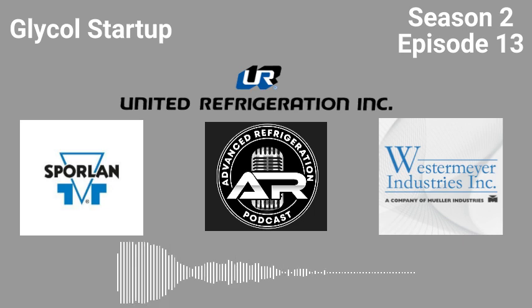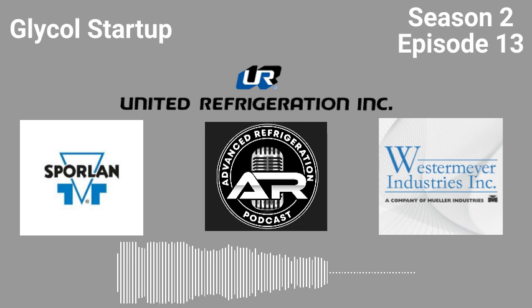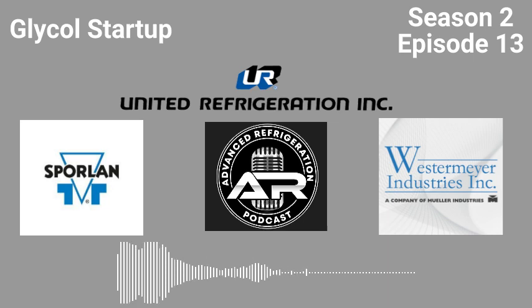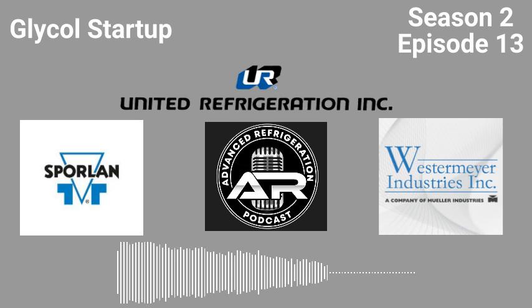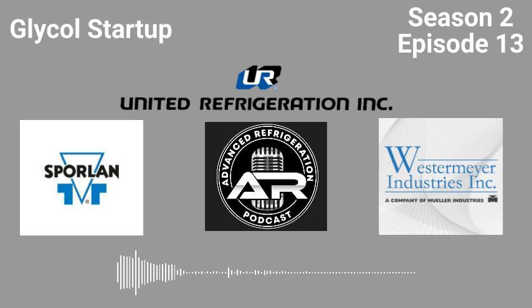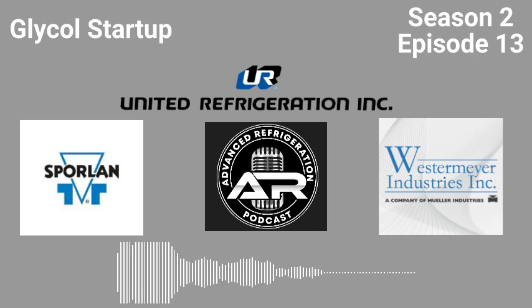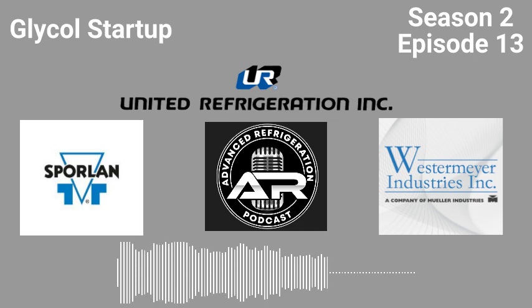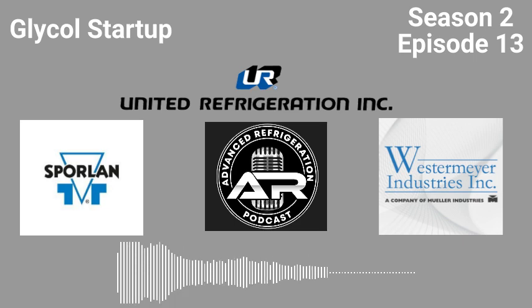But if your rack room is on the ground, it's not going to be your best place to bleed, because remember, air is always going to get stuck in the highest point. So you want to put bleeders all over the store. Like if you're putting in a new glycol store and you're not putting bleeders on the mains and bleeders on the tops of the risers, you're only screwing yourself on startup, because it costs 10 times more to bleed that store than it's going to cost for those bleeders later on. So after I get everything bled and everything looks good, then I'll start bumping the pumps. And generally what I'll do is I'll overcharge the system.